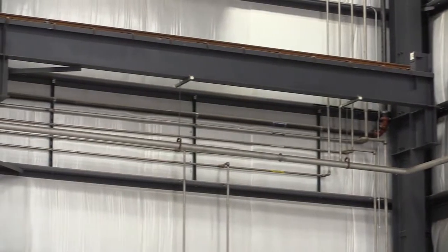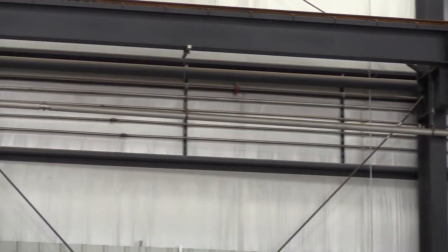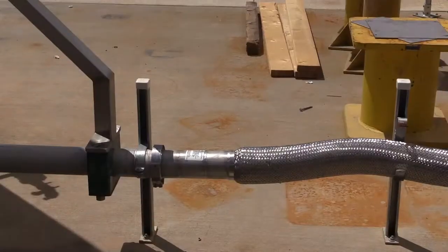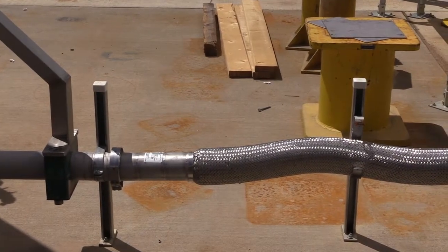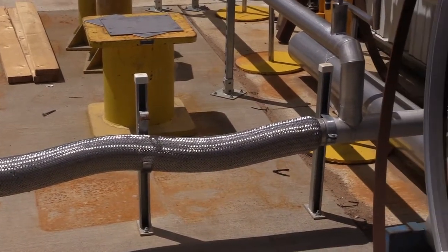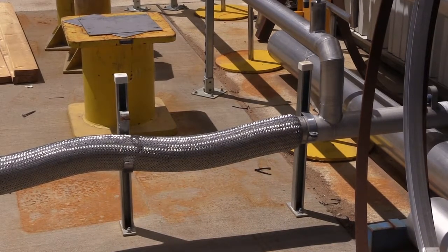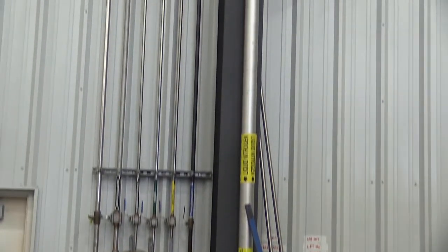Some design rules of thumb are: recommended system slopes should utilize 1 inch slope per 10 feet. This slope should always run uphill to the cryo vent. Traps should never be generated anywhere in the system. Even sagging flex line or improperly supported pipe can cause a trap area. Hangers and supports should be spaced at 10 feet or less when installing the system. One cryo vent should be planned for every 100 feet of pipe run.